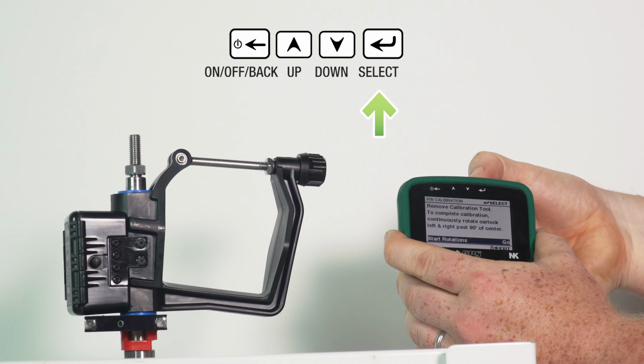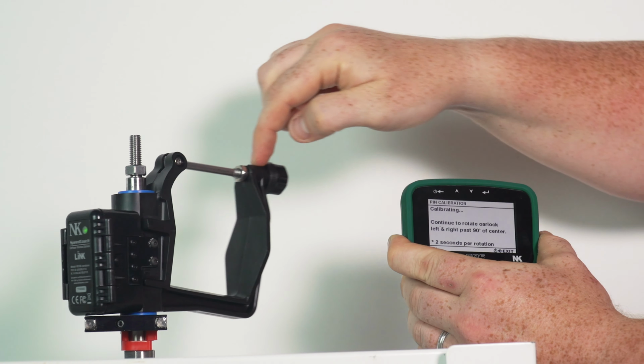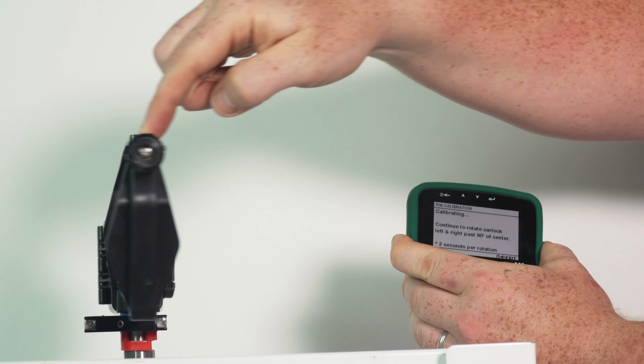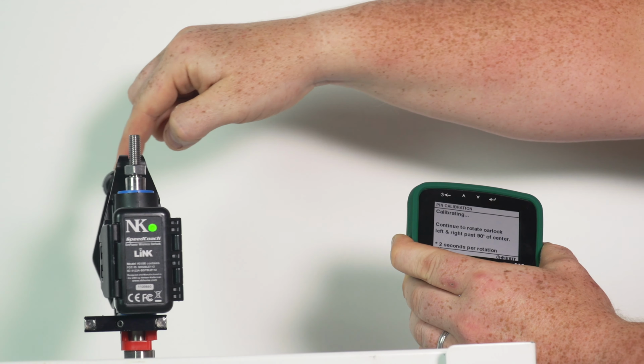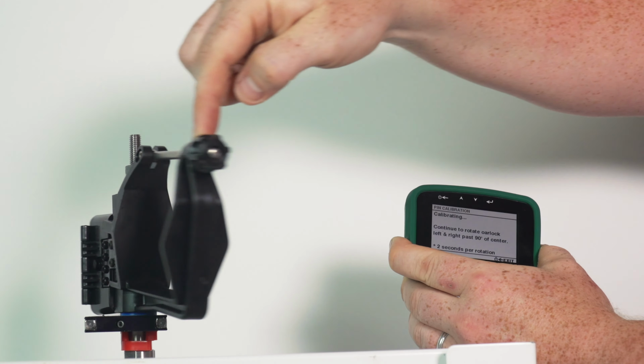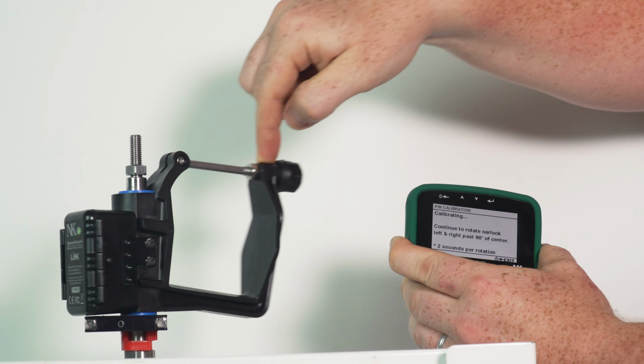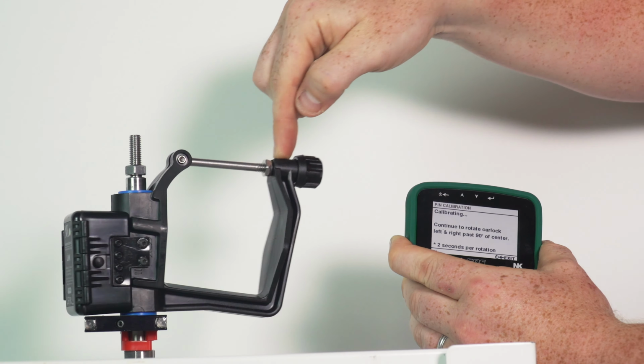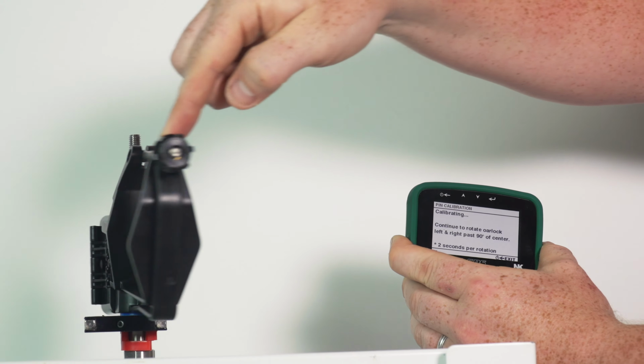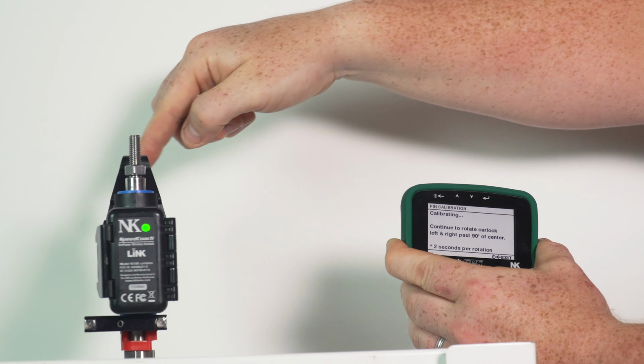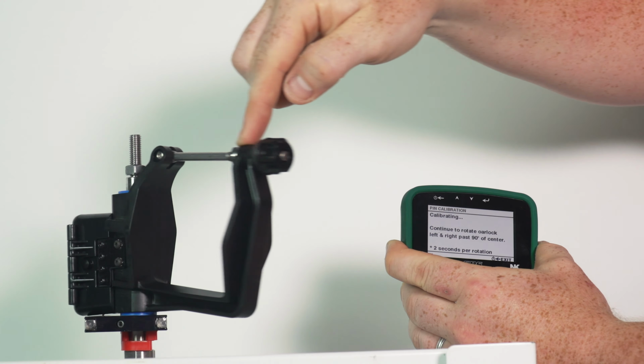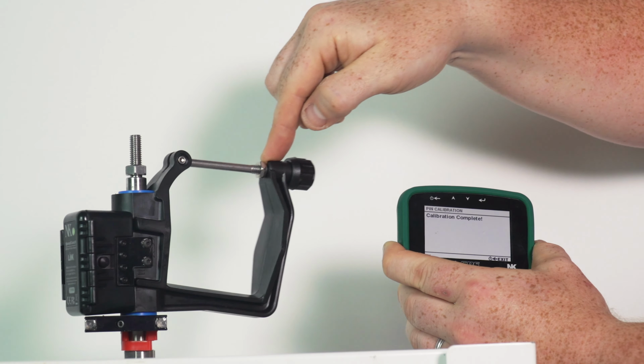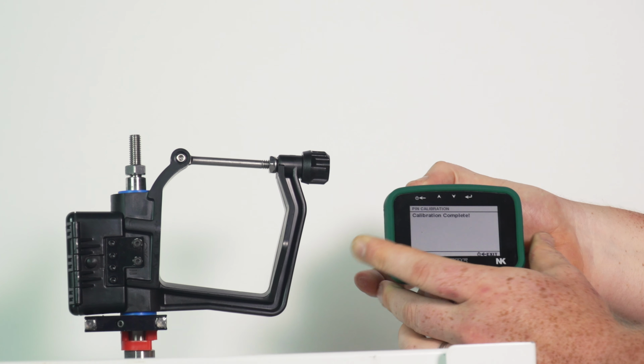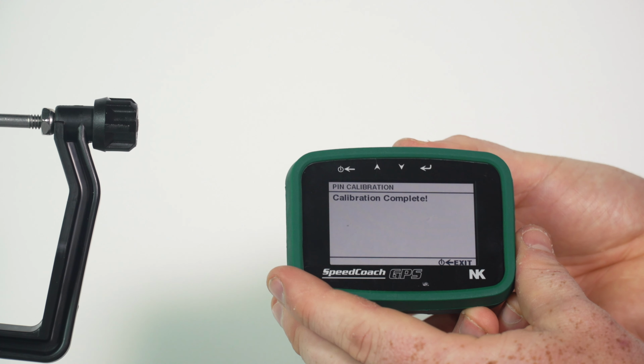Each rotation should take 2 seconds to do a full single rotation. So we press go, and we move the Oarlock back and forth. One thing to manage is you want this to be a smooth movement with no stopping and starting, just back and forth at a single speed, and it'll eventually say calibration complete when all the points have been made.